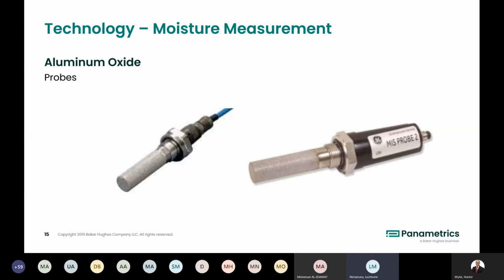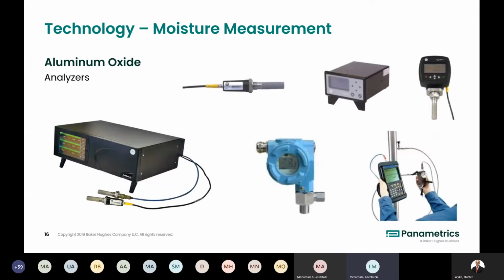So it allows you to make a number of measurements apart from dew point. You can measure parts per million, RH, parts per million by weight or by volume, and any other derivatives of that, pounds per million standard cubic feet, et cetera, et cetera. So they're kind of the core sensors. So if you just move on to the next slide there.